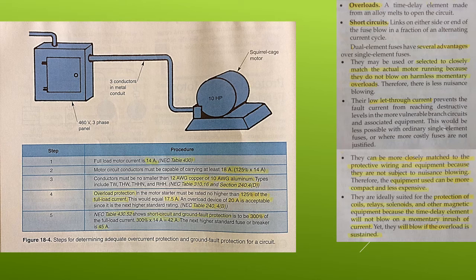The maximum fuse or breaker size permitted for short circuit or ground fault protection is 300% of the full load current rating. For example, look at Figure 18-4 on the left side of the screen. Note that the procedure for determining conductor size and the protection is the same as for the larger motor used in our previous example. It makes no difference that the motor type and supply voltage are different.